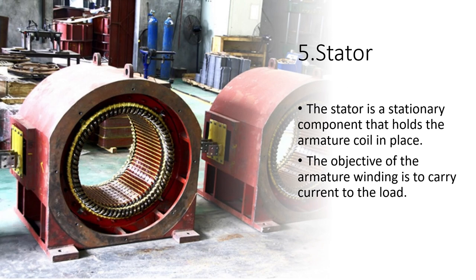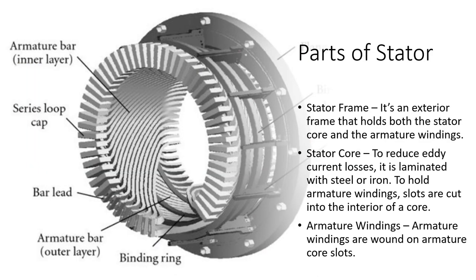Number 5: Stator. The stator is a stationary component that holds the armature coil in place. The objective of the armature winding is to carry current to the load. The stator frame is an exterior frame that holds both the stator core and the armature windings. The stator core is laminated with steel or iron to reduce current losses, and slots are cut into the interior of the core to hold armature windings, which are wound on those armature core slots.